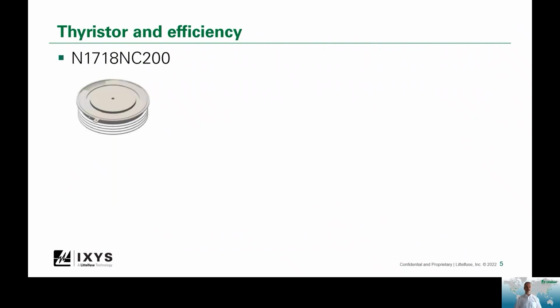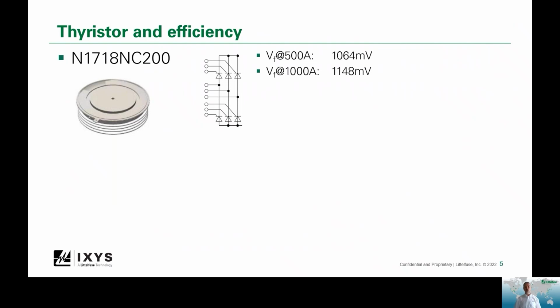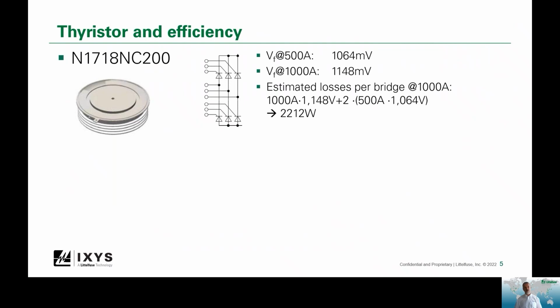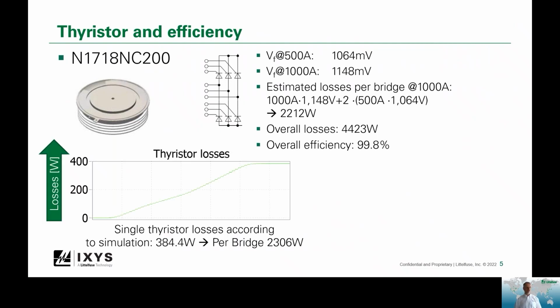The thyristor is a nonlinear piece of hardware. So building a B6 or B12 bridge from a thyristor, the forward voltage at a 500 amp forward current is in the regime of 1 volt. But due to the nonlinearities, even at twice the current, 1000 amps, the forward voltage only grows by 150 millivolts. Let's assume an estimation: this leads to about 2.2 kilowatts of losses in a B6 bridge. Overall losses, because there are 2 bridges involved, are 4.4 kilowatts, which leads to an overall efficiency of 99.8%. So how good is this guesstimation? Well, supported by simulation, the thyristor losses turn out to be 384 watts per thyristor or 2,300 watts per bridge. So the guesstimate is pretty accurate if the simulation is considered precise.